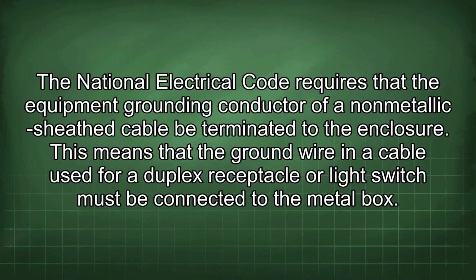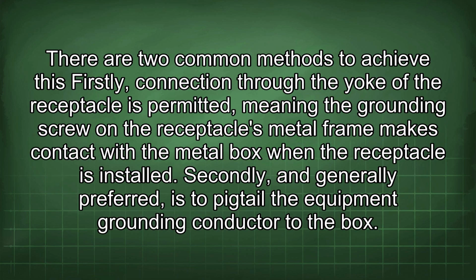The National Electrical Code requires that the equipment grounding conductor of a non-metallic sheath cable be terminated to the enclosure. This means that the ground wire in a cable used for a duplex receptacle or light switch must be connected to the metal box. There are two common methods to achieve this. Firstly, connection through the yoke of the receptacle is permitted, meaning the grounding screw on the receptacle's metal frame makes contact with the metal box when the receptacle is installed.